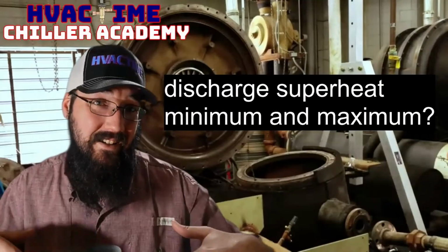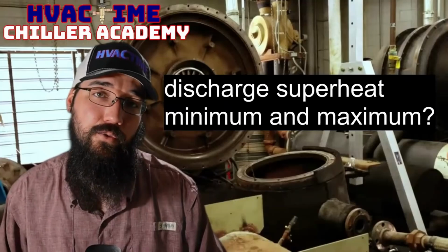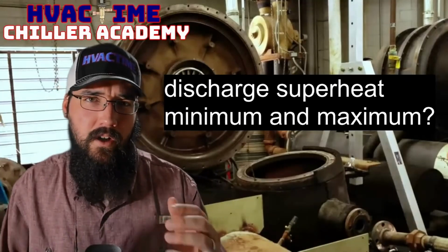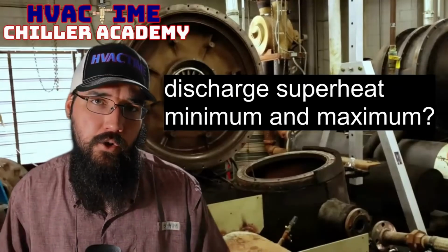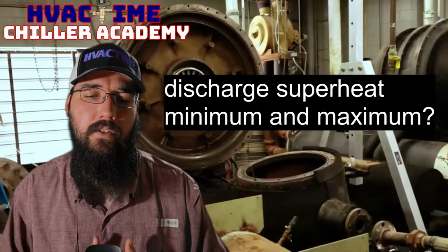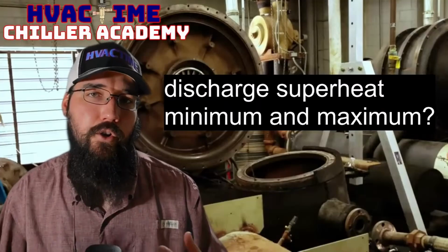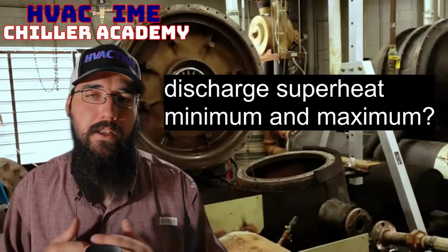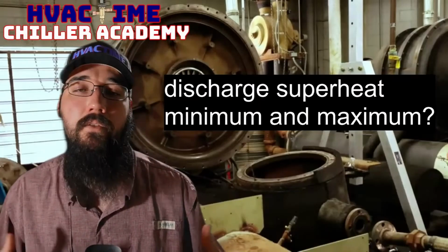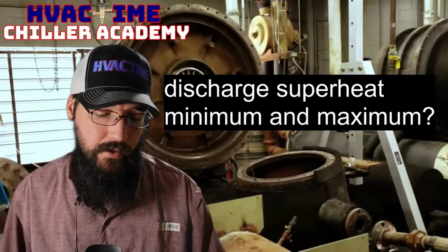But it would definitely tell me that if I'm on the low end of the load but I'm still having a high discharge superheat, that would make me want to ask questions. I hope that makes sense. This is where we have to apply our human logic and our understanding and experience of these things, because the circumstances are very dynamic in what could or couldn't be. That's why you are paid to be in the role that you're in, and that's why we're having a conversation like this, to help build on these things and get you a better foundation.